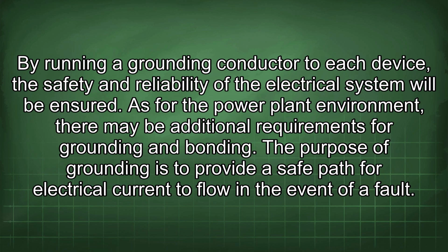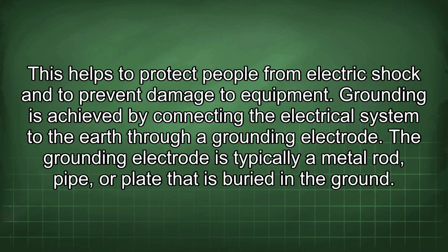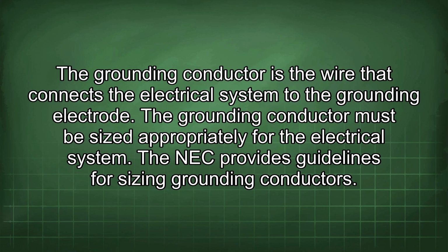The purpose of grounding is to provide a safe path for electrical current to flow in the event of a fault. This helps to protect people from electric shock and to prevent damage to equipment. Grounding is achieved by connecting the electrical system to the earth through a grounding electrode. The grounding electrode is typically a metal rod, pipe, or plate that is buried in the ground. The grounding conductor is the wire that connects the electrical system to the grounding electrode. The grounding conductor must be sized appropriately for the electrical system. The NEC provides guidelines for sizing grounding conductors.